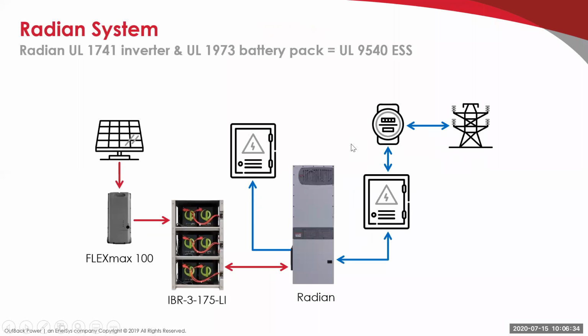Very simple, straightforward. A Radian system, which is a storage system, is a little more complicated in that the DC from the PV has to first go through what's called a charge controller. The charge controller is basically a step-down DC to DC transformer. This charge controller, the FM100 or FlexMax 100, takes 300 volt strings, and that gets sent down to battery voltage, which with the Radian is always a 48 volt battery. So 300 volts in, 48 volts out to the battery.